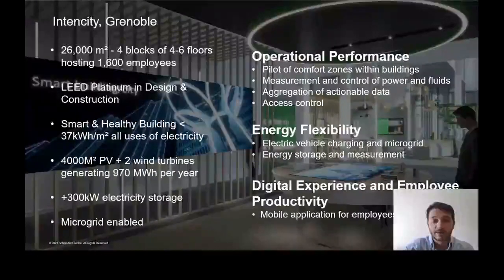In order to offset that, we've deployed 4,000 square meters of photovoltaic panels combined with 2 wind turbines, and those will generate around 970 megawatt hours per year. If you do your maths, you will see that overall it is net zero. The building is autonomous, but of course, because we need to be able to manage that generation with the consumption, we've deployed 300 kilowatt of energy storage, and there's a microgrid overall.